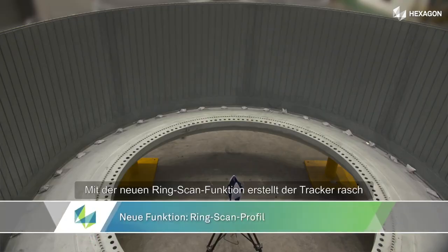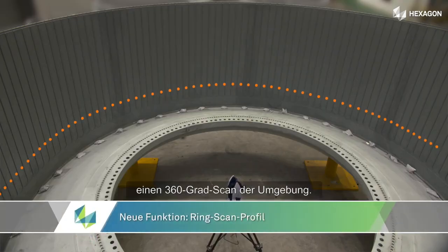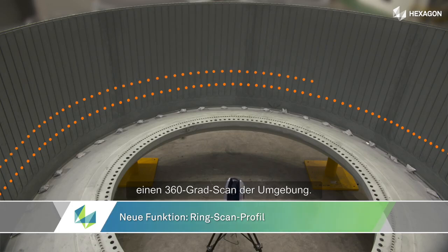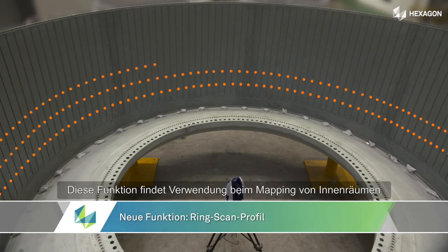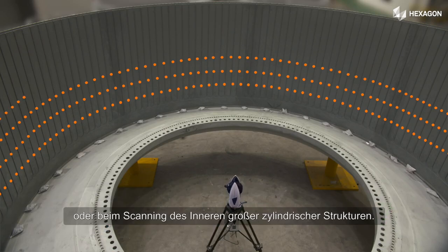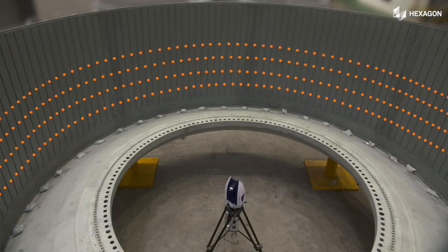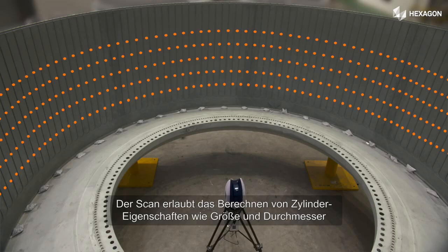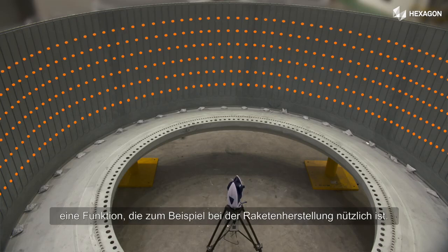The new ring scan function allows the tracker to quickly create a 360-degree environment scan. This function can be used in interior mapping or to scan the interior of a large cylindrical structure. The scan would allow for the calculation of properties of the cylinder, such as size and diameter, useful for example in rocket manufacturing.